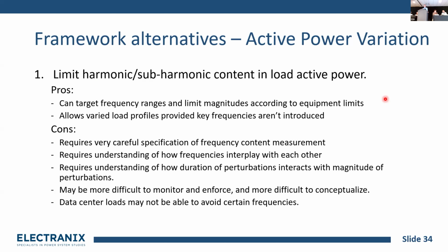The first one is to say, we know we're really worried about certain frequency ranges - subharmonics or the subsynchronous range because of synchronous machine torsionals, and machine mode oscillations and so on. So we could say, for these frequency ranges you can have a fine filter or a wider filter, but for these frequency ranges, limit the magnitude of the frequency content of the load's active power fluctuation. You can get quite sharp with those criteria, and you can probably allow fairly large variations in active power that avoid the key frequencies you're worried about.